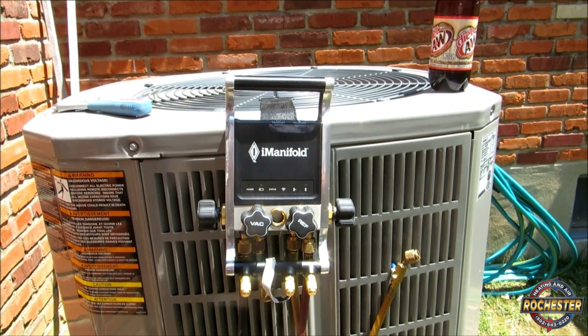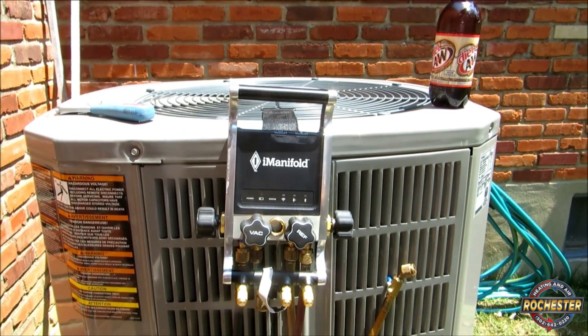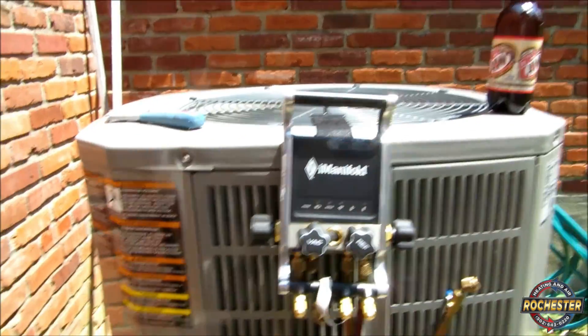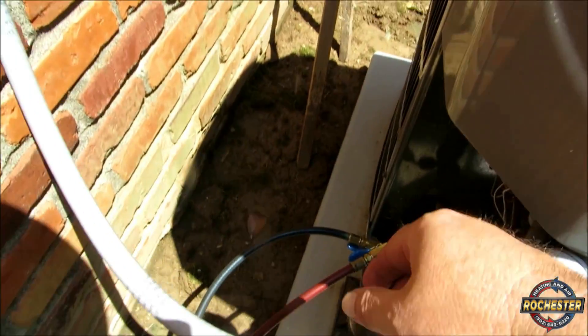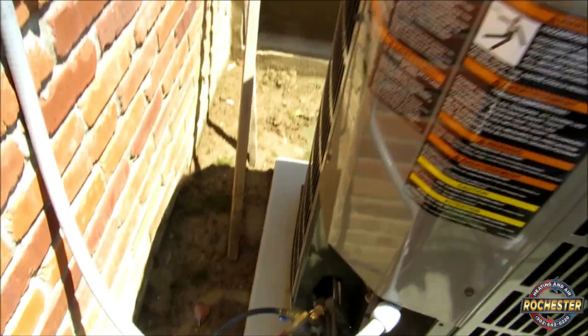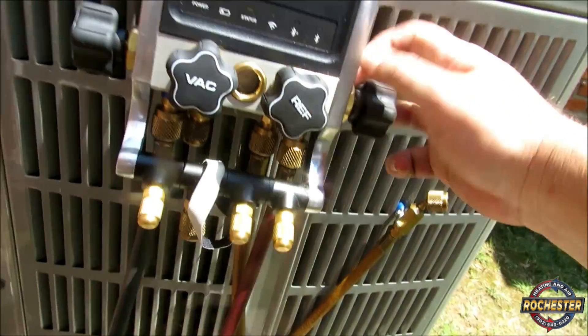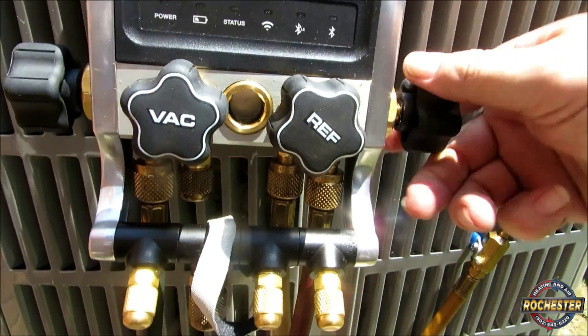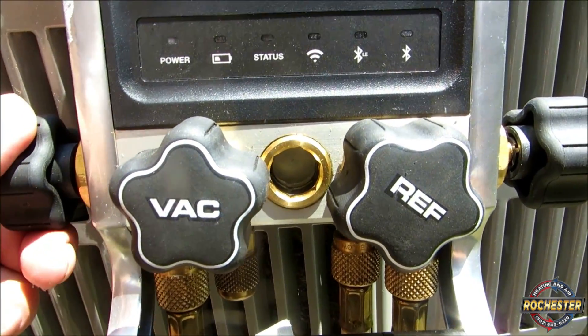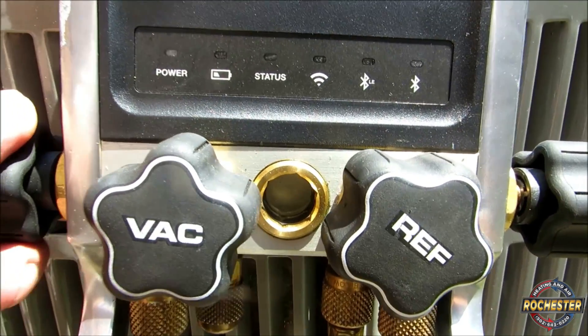I wanted to share this with you real quick as well. I've had a few people ask me what I do before I unhook. I've got my Cooper-Atkins temperature probes off. With this sight glass, what I actually do is I'll come down here to my liquid line, I'll actually turn off my ball valve here — I've got that in the off position as you can see. I'll open my liquid here, and keep an eye on the sight glass. Then I'll open up my suction line, and hopefully it'll suck it all back into the unit — or at least 95% of it.